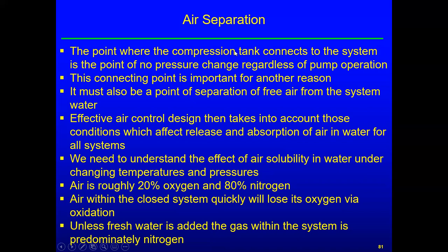But unless you have a constant source of oxygen, it's not enough to hurt anything on the initial fill. And so then you wind up with just nitrogen pretty much circulating around in the system because nitrogen doesn't react with much of anything, at least inside of a piping system. So unless fresh water is added, the gas within the system is predominantly nitrogen. So that's what we're actually trying to control here.